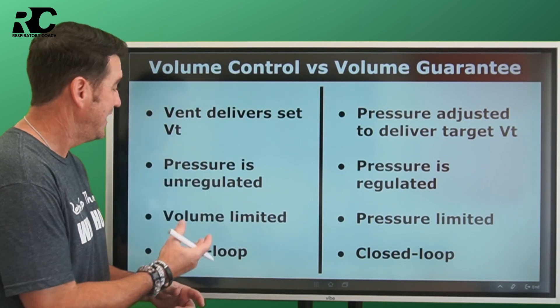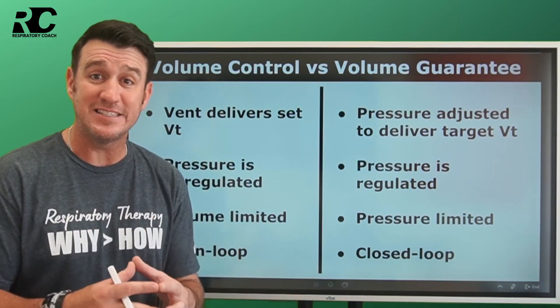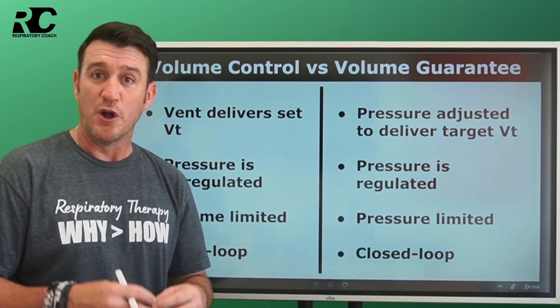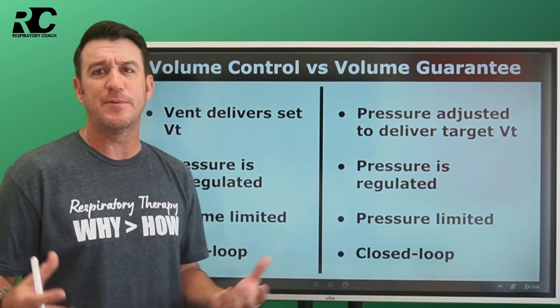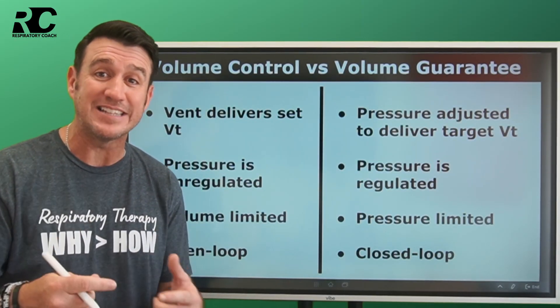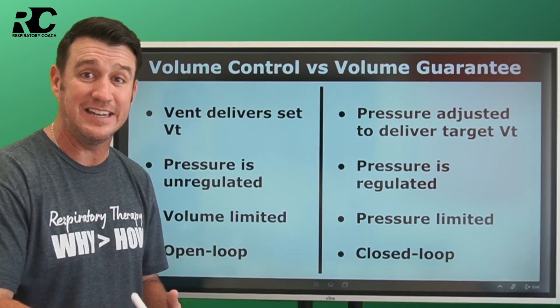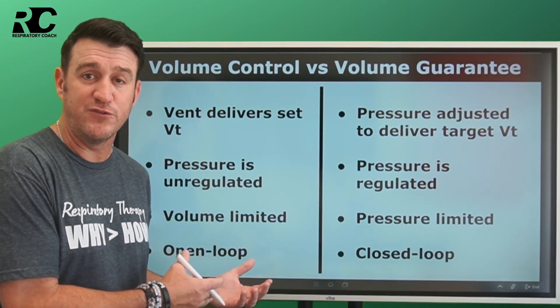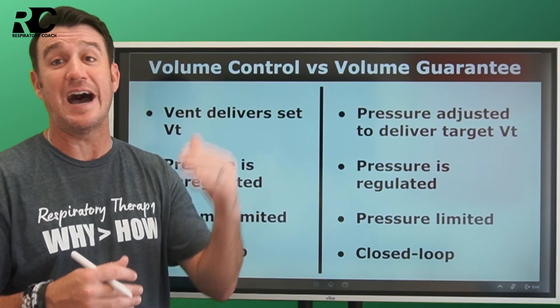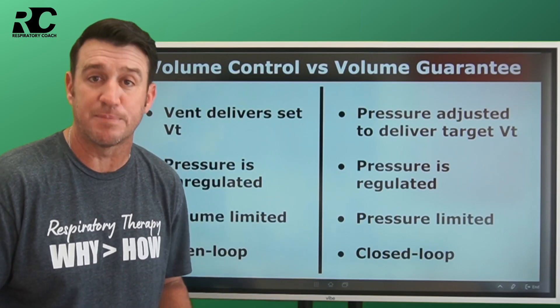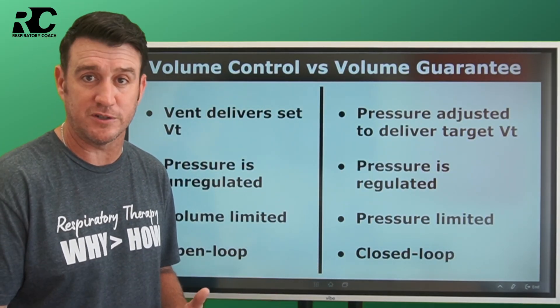Volume control is not pressure regulated — pressure is unregulated. That means when the ventilator delivers the set tidal volume, pressure can go as high as it's going to go based off of compliance and resistance. We do have a high pressure alarm that will notify us if that alarm is reached, but that is not innately built into the mode. If you set that alarm as high as it could go, the pressures could go as high as they'll go. Nothing would stop the volume from being delivered based on pressure. That's the way volume control works.